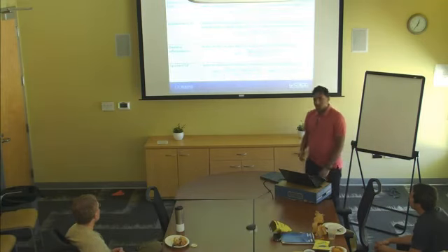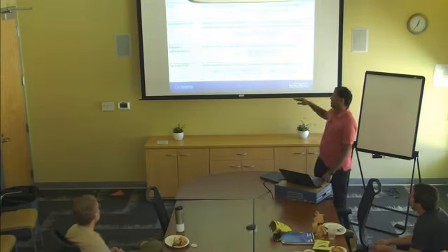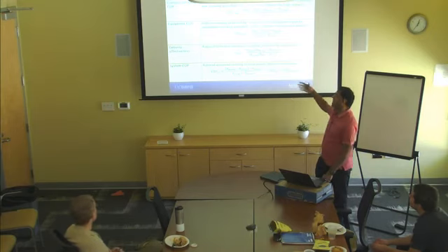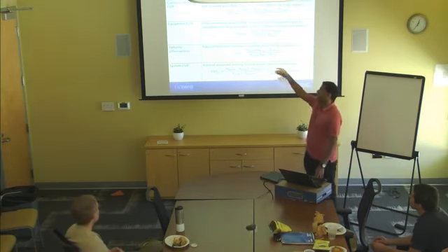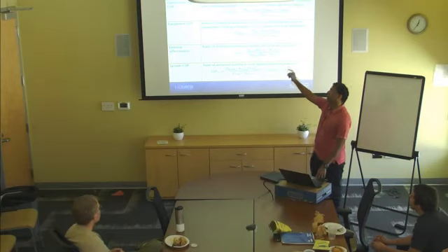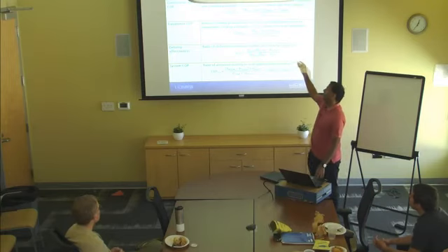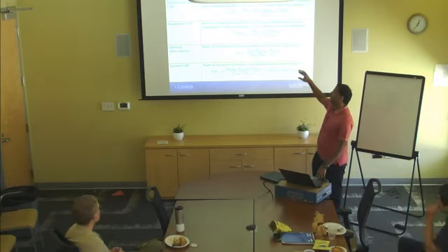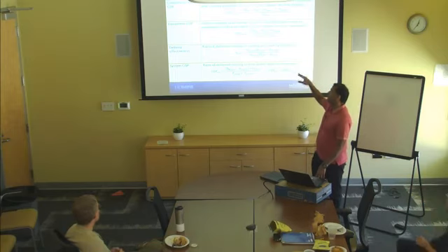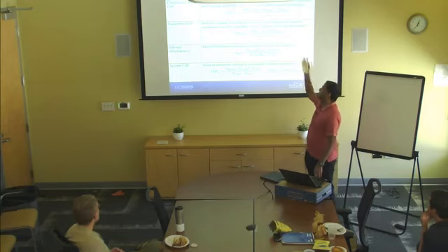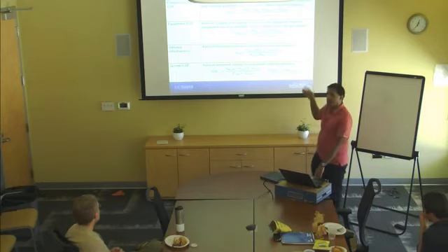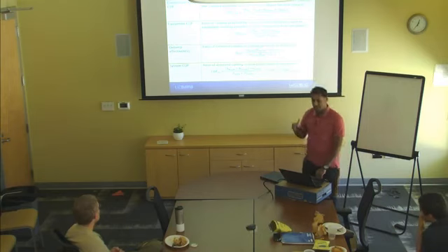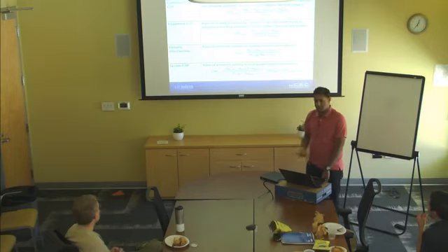So based on that, I tried to define 4 efficiencies. The first efficiency is just looking at the compressor only. So the COP of the compressor, which is the ratio of the cooling delivered by the evaporator to the power input to the compressor, where the cooling delivered doesn't include the fan power or the fan heat. And this is the kind of efficiency that we normally study in thermodynamics classes.